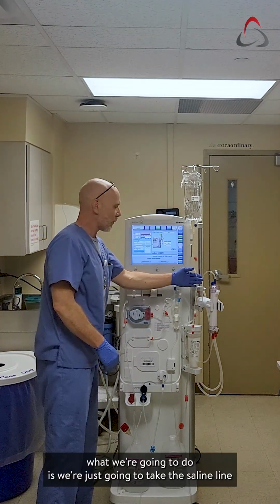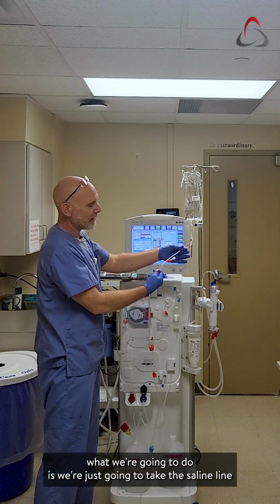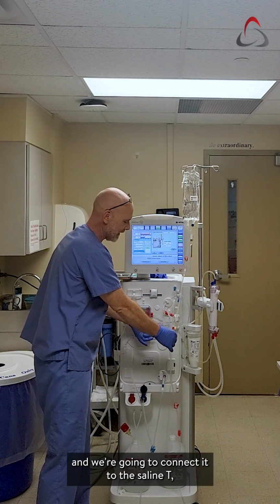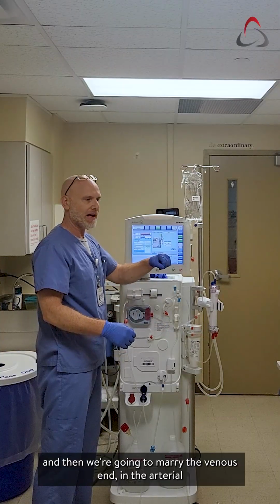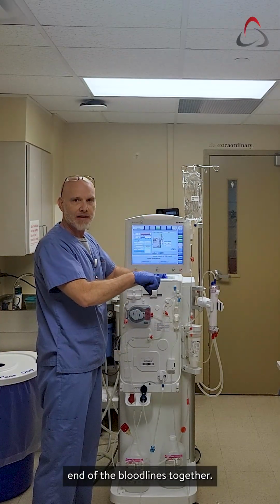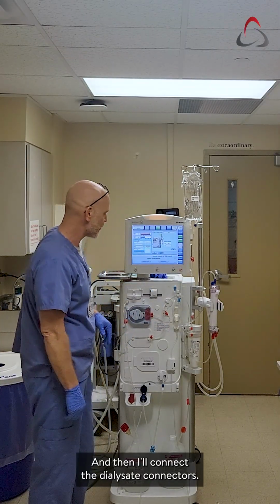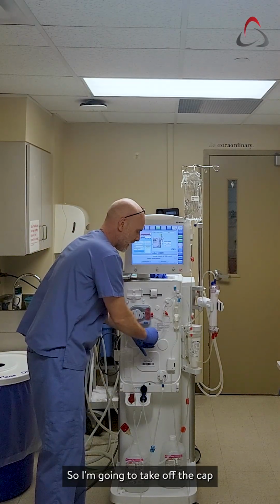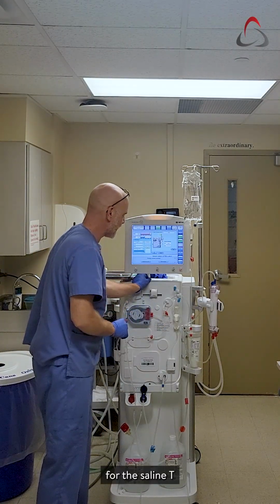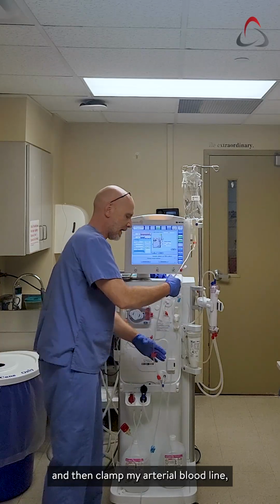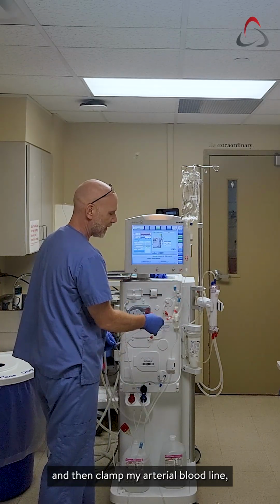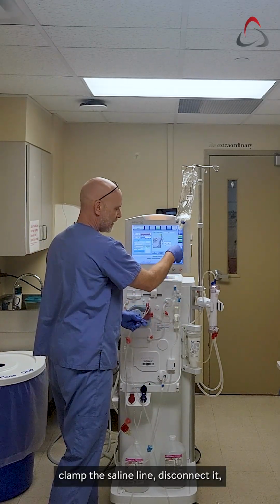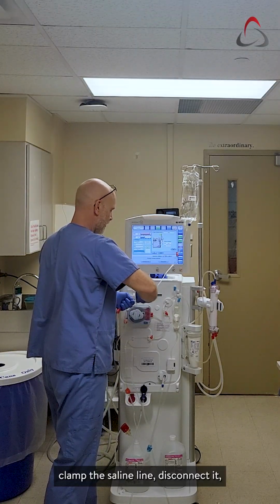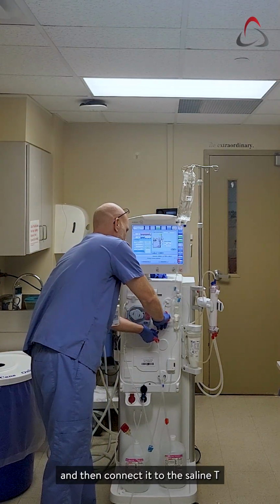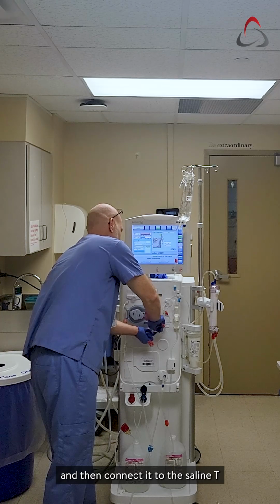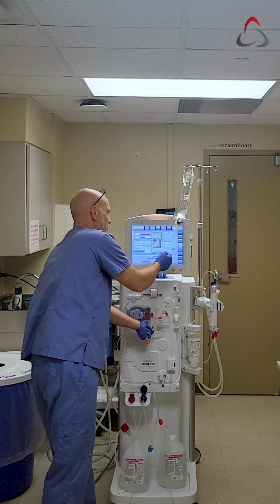So to put it into recirculation, we need to reconfigure the lines and hook up the dialysate connectors. What we're going to do is we're just going to take the saline line and we're going to connect it to the saline tee, and then we're going to marry the venous end and the arterial end of the blood lines together, and then I'll connect the dialysate connectors. So I'm going to take off the cap for the saline tee and then clamp my arterial blood line, clamp the saline line, disconnect it, and then connect it to the saline tee and open your clamps.